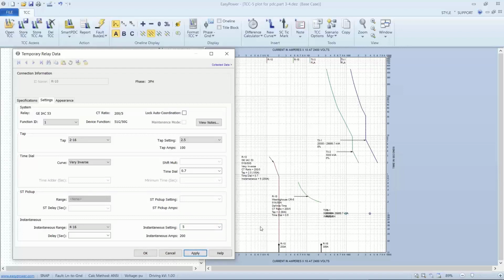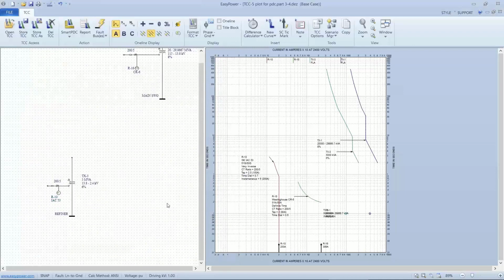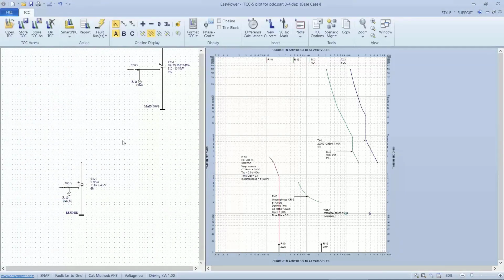Yeah. So at the maximum 200 amp, it will give us an instantaneous trip on that part of the circuit. So again, that allows us to verify the downstream device was causing the ground current that was being sensed upstream. So again, this is a policy or a judgment that you make based upon how much coordination you need to have between these systems on different buses and different transformers, and how important it is to have instantaneous protection somewhere downstream to keep it from affecting the upstream device.